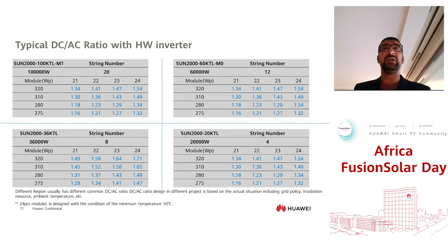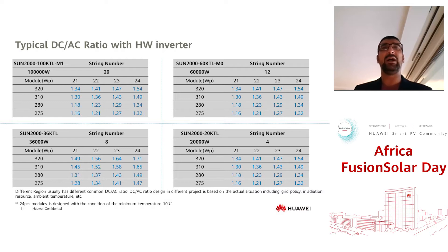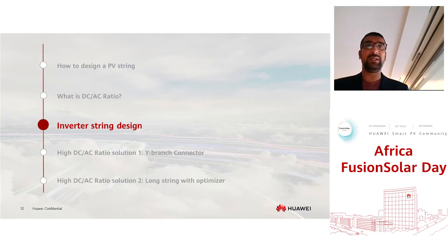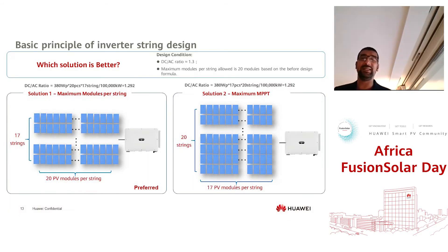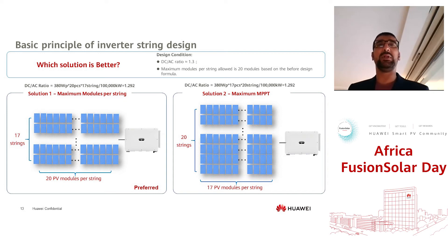For a reference case I'll select the 60KTL-M0 inverter with the 280W PV module. This particular inverter has 12 strings, and connecting around 22 PV modules per string provides around a 123% DC to AC ratio. Now looking in detail at the inverter string design itself — the principle has many configuration options due to the multiple MPPTs and multiple strings available per inverter.